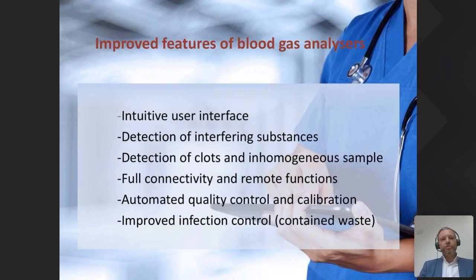We now are very used to automated quality control programs and calibration. Again, this allows for periodic quality control throughout a 24-hour period, and corrective actions are built into that in terms of flush cycles and trying to correct calibration errors so that you can get maximum uptime from your machine. And of course, improved infection control.